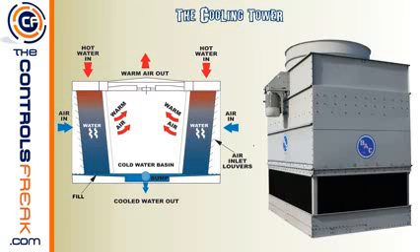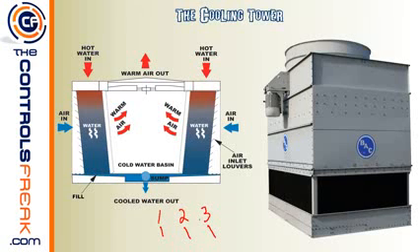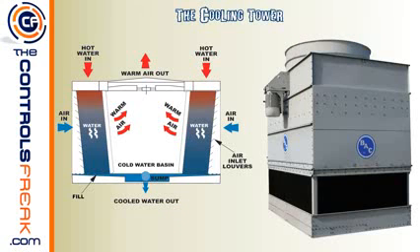Control strategies for cooling towers often involve multiple towers side by side. You can stage them — as it gets warmer, you call on another tower — or dedicate one tower per chiller. You might also have multiple fans on a single cooling tower cell. Another strategy involves a bypass valve, which normally allows the hot water to come in at the top of the tower.